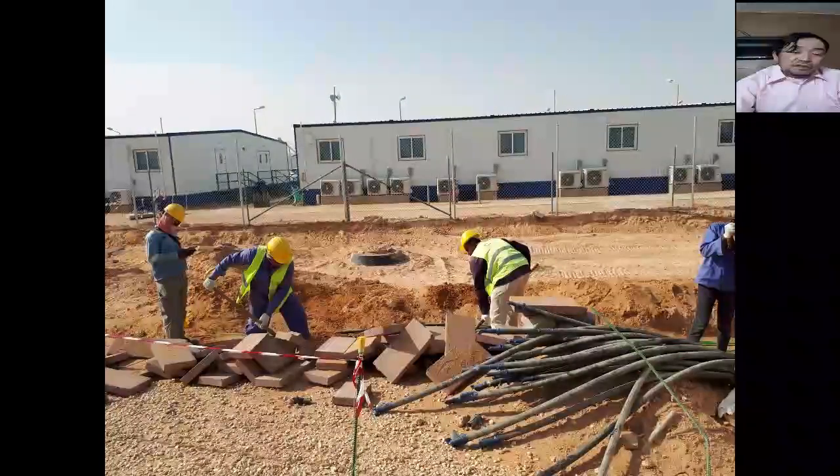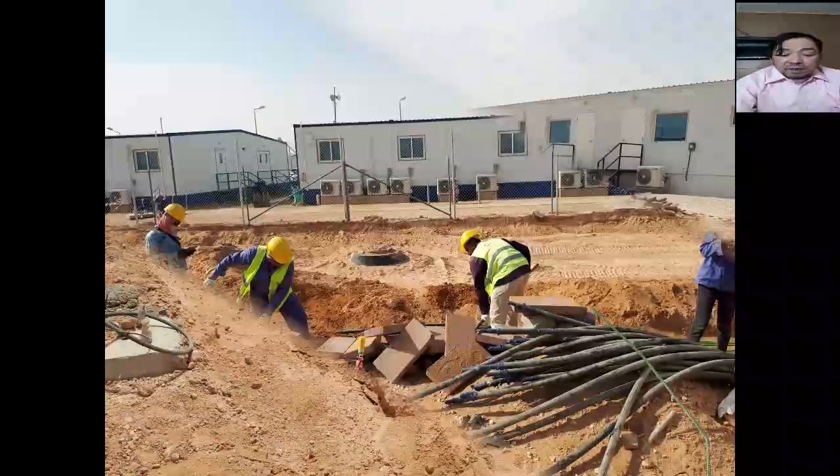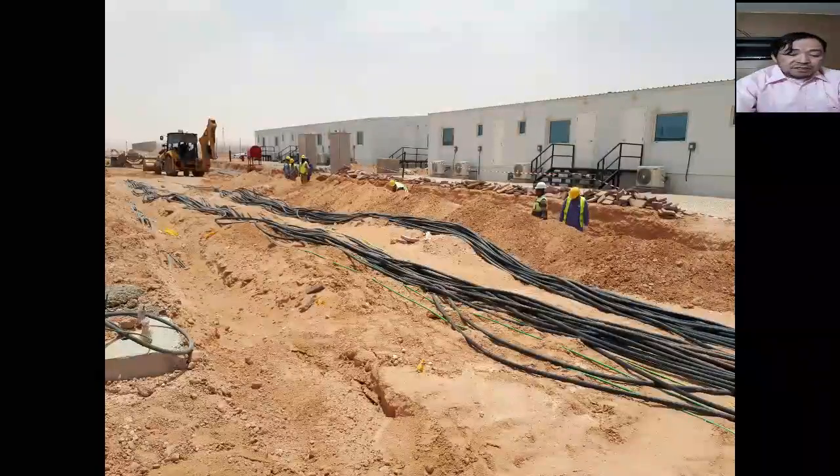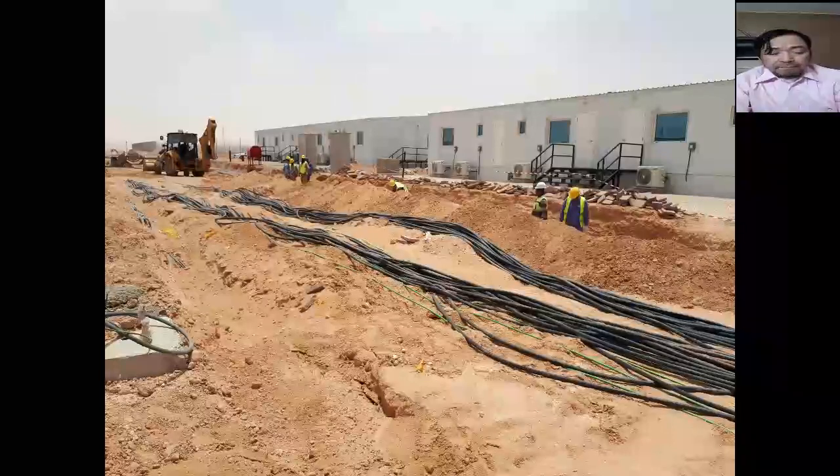There are other considerations as per SAES-P-104 section 10. In case of rocky areas where digging must be minimized, or in areas where Table 2 would result in cable being below the water table, or to avoid other obstructions such as other cables or utility, cables may be installed at a lesser depth than mentioned in Table 2 by means of the following.